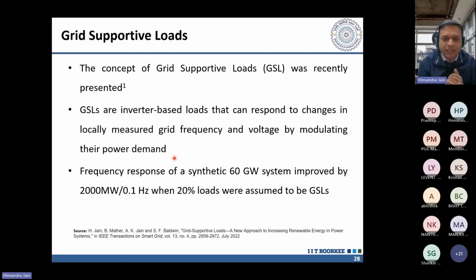That's when we came up with this idea of grid supportive loads, which is also described in a paper we published. The idea was that since we are using these inverter based assets, they have a controller, they have a chip, I can program it to do whatever I want. So I can even measure frequency locally, I can measure voltage locally. And frequency is a global measure, meaning if you measure the frequency here, under steady conditions the grid frequency across India is largely going to be the same. There might be small variations, but largely the frequency is going to be the same.